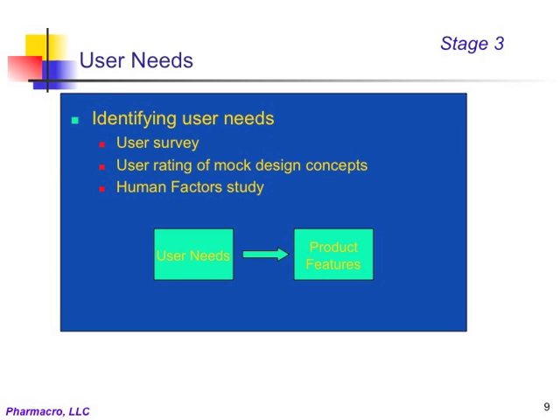The FDA is particularly concerned about safety issues arising out of improper use of medical devices caused by suboptimal product design. After the user needs are identified, they are clearly documented and the information is used to define features in the device that would meet the user needs.